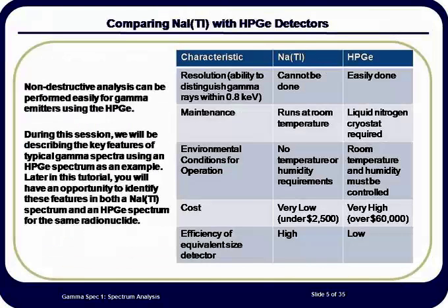Compared to the sodium iodide detector, the newer high-purity germanium detectors are relatively expensive, more difficult to operate, require constant liquid nitrogen conditions to operate, and are sensitive to environmental conditions of the counting room. However, the big advantage of the high-purity germanium detector is that it can resolve 2 gamma rays that are within about 0.8 keV of each other. This is a significant advantage, as many samples have naturally occurring decay products of uranium and thorium that have multiple gamma rays.